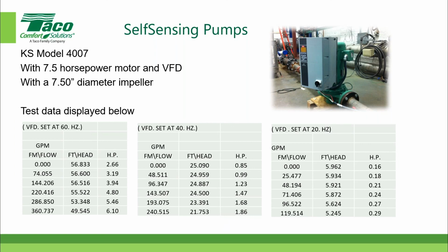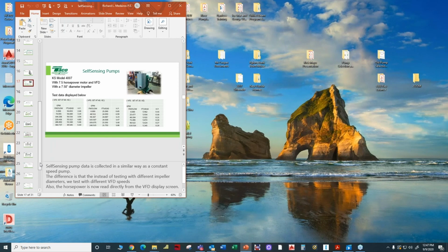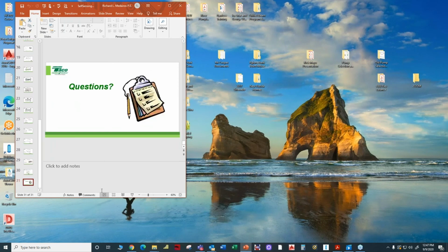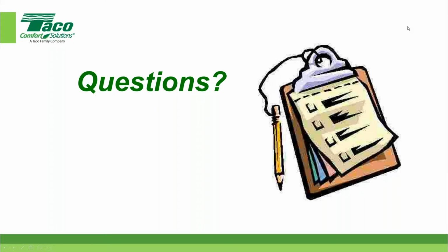How accurate would you say the flow value is compared to a traditional DP sensor system? The flow values are within 3% of the published values. Good stuff. Any other questions out there? Actually, I think you answered this one, but this is probably a good one to re-answer. In the menu of the drive, is it possible to change the self-sensing operation from constant flow to constant head, or vice versa? Yes.